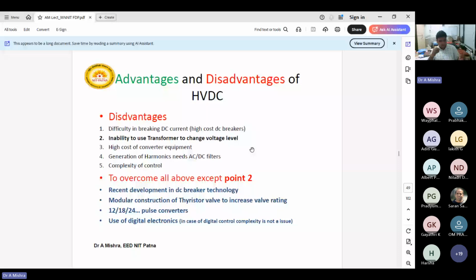So, recent development in the DC breaker technology: with the development in the technology, DC breaker cost is also getting reduced. The second one is the modular construction of the thyristor valve to increase the valve rating. Modular structure means if you are bothered about the rating and all, instead of using one big system together, use the modular structure.